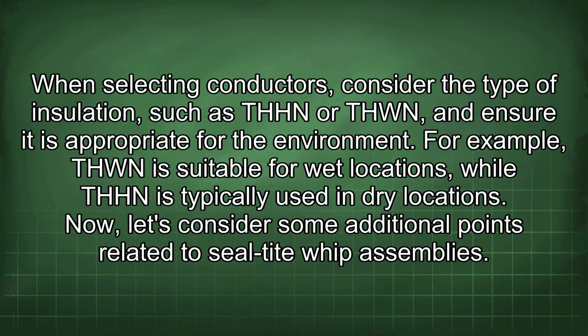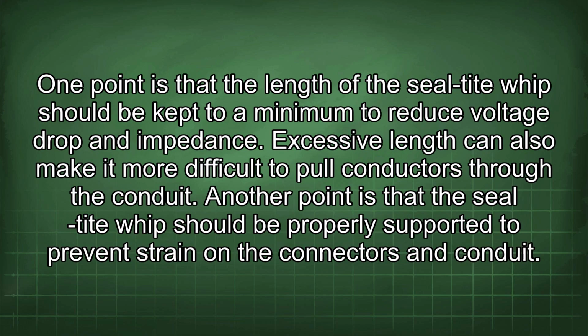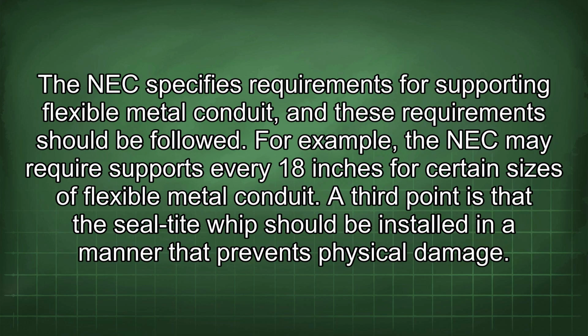Now, let's consider some additional points related to Seal-Tite whip assemblies. One point is that the length of the Seal-Tite whip should be kept to a minimum to reduce voltage drop and impedance. Excessive length can also make it more difficult to pull conductors through the conduit. Another point is that the Seal-Tite whip should be properly supported to prevent strain on the connectors and conduit. The NEC specifies requirements for supporting flexible metal conduit, and these requirements should be followed. For example, the NEC may require supports every 18 inches for certain sizes of flexible metal conduit.